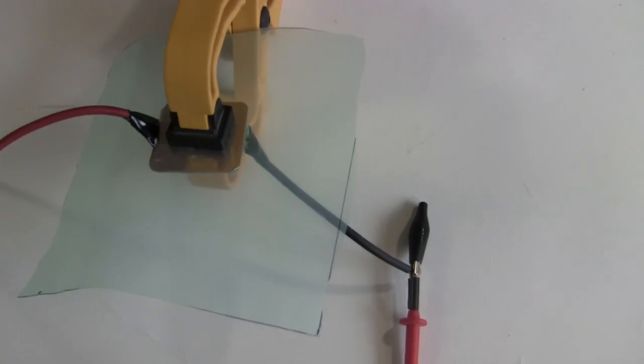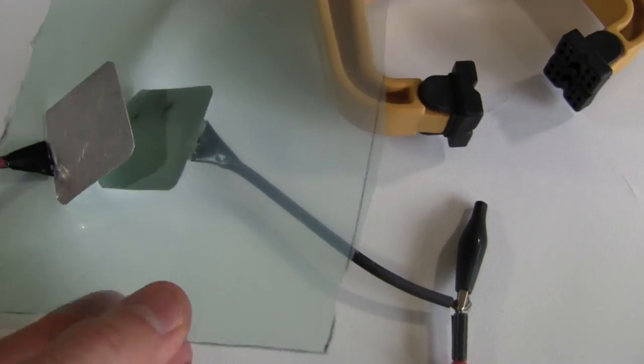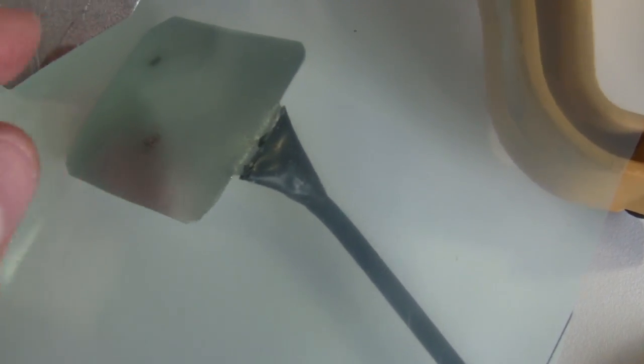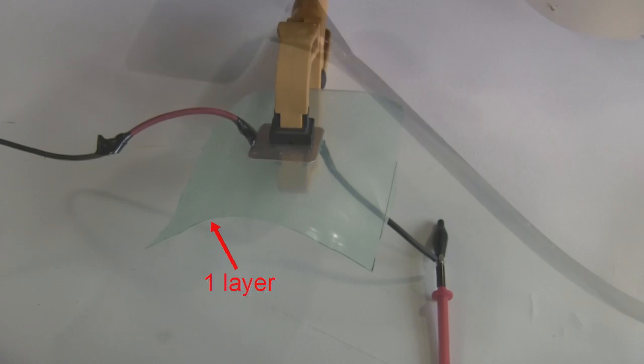So let's open it up and see the damage. Now there we can see it. Brown spot right there through the dielectric, brown spot on the middle layer, and a dark spot right there as well. And I believe it's a hole. Yep.